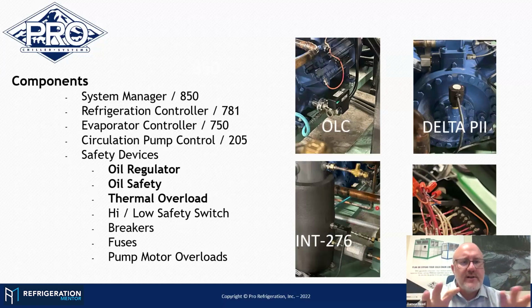The 250 horse compressors are parallel pipe. We have an INT 276, just a prism that monitors the oil level in the oil reservoir. So if the oil level drops to this level, it's not going to shut down the equipment, but it is going to give you a low oil warning light on the front of the system. Just means, hey, I look at my oil system. I may need oil. Where did the oil go? You kind of go into your troubleshooting steps at that point.